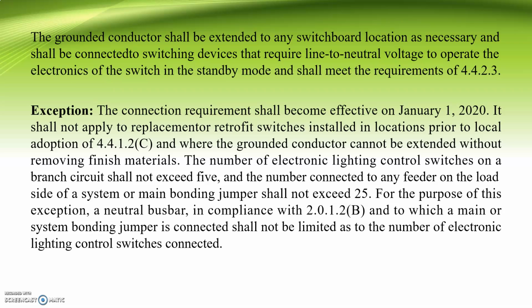So the grounded conductor shall be extended to any switch location as necessary and shall be connected to switching devices that require line to neutral voltage to operate the electronics of the switch in the standby mode and shall meet the requirements of chapter 4.4.2.3. The exception for this: the connection requirement shall become effective on January 1, 2020. It shall not apply to replacement or retrofit switches installed in locations prior to local adoption of chapter 4.4.1.2c and where the grounded conductor cannot be extended without removing finished materials.